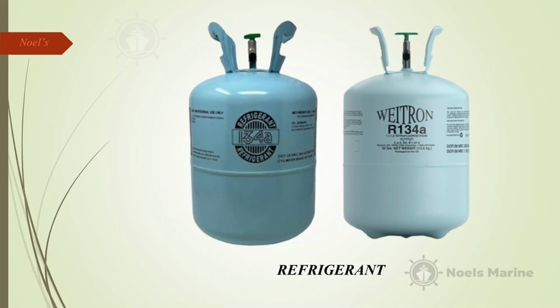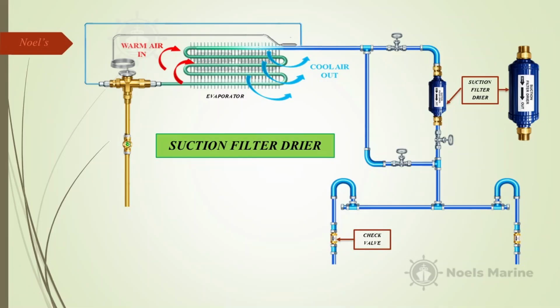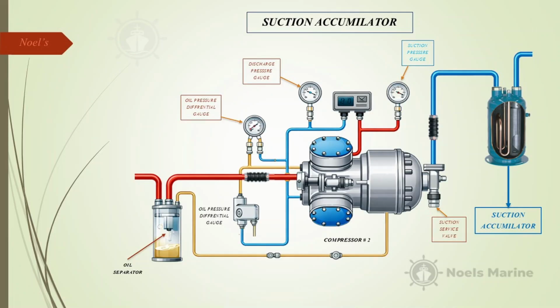We're moving toward the compressor through the suction line, and we hit the bouncers. The security guards of the system? Right, the suction filter dryer and the suction accumulator. Why do we need security here? Well, the accumulator plays a vital role. It acts as a safety tank to catch any liquid refrigerant that might not have boiled off in the evaporator. Compressors can only handle gas. Right, because you can't compress a liquid. Exactly. If liquid hits those compressor pistons, it's called liquid slugging. It will absolutely destroy the compressor. The accumulator stops that from happening. It also stores excess refrigerant during low-load conditions.